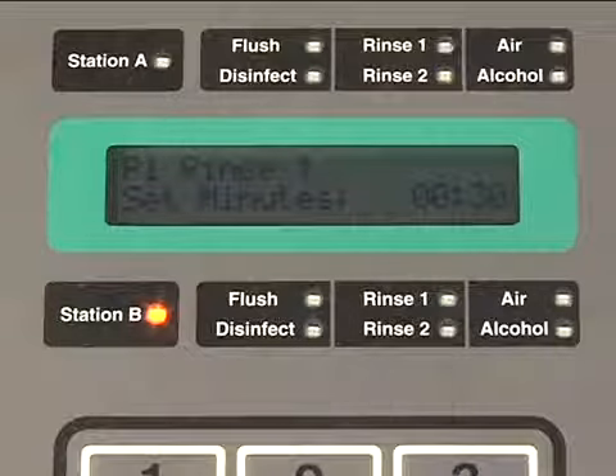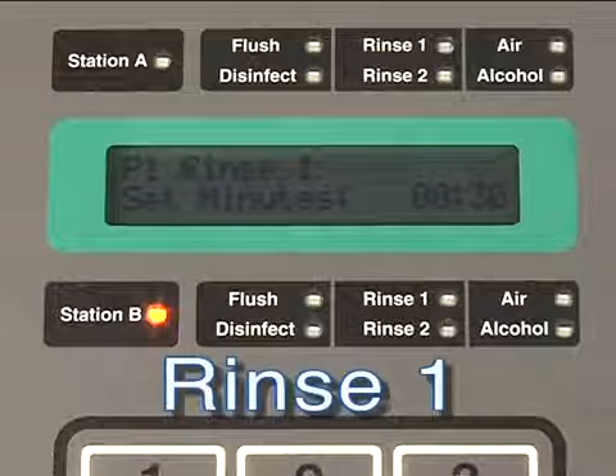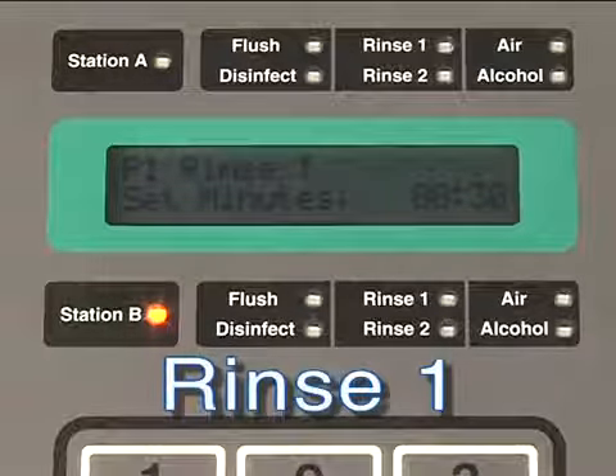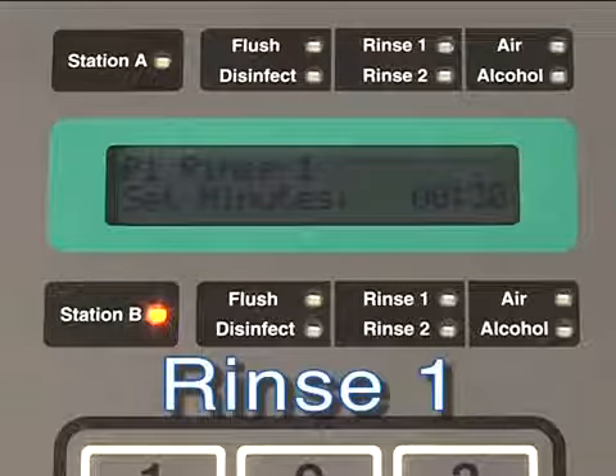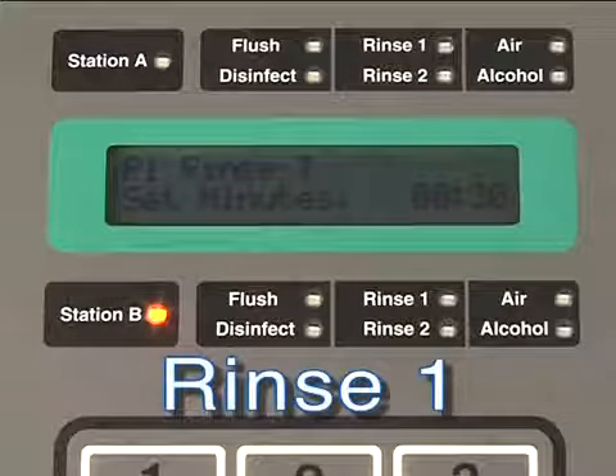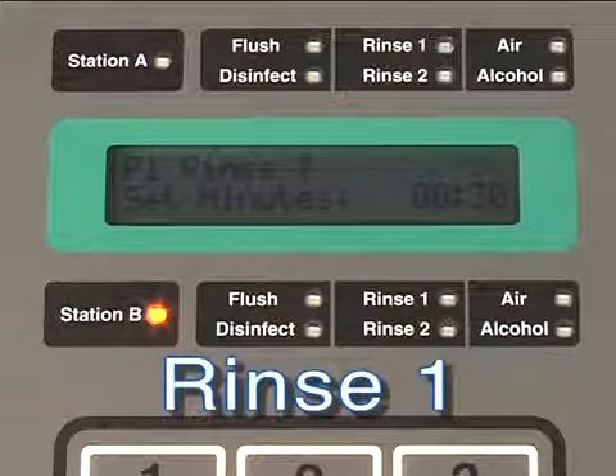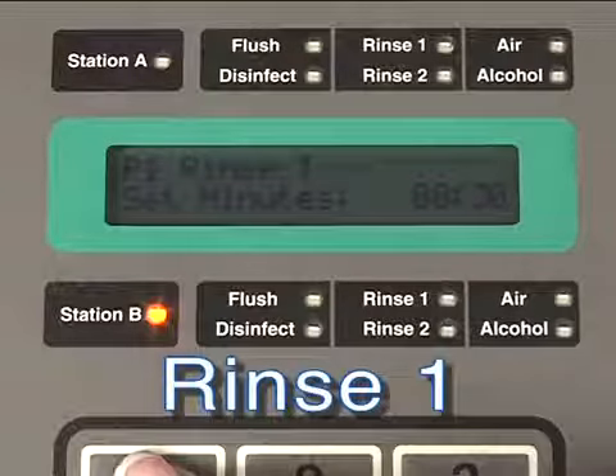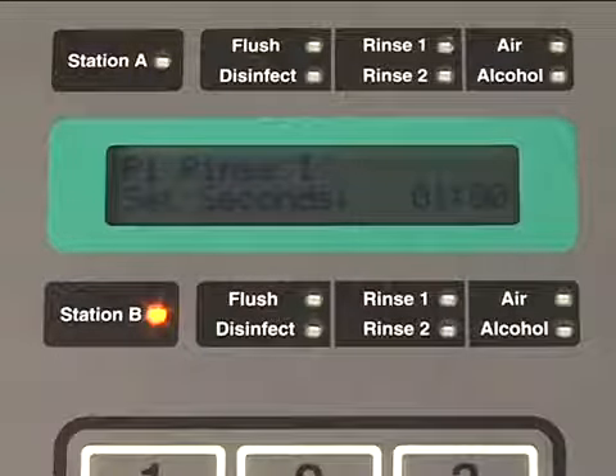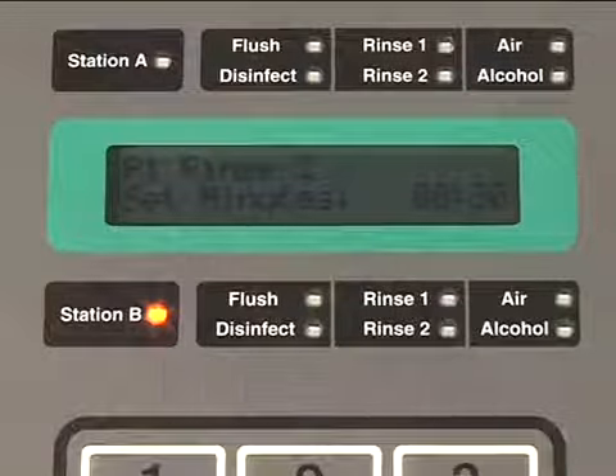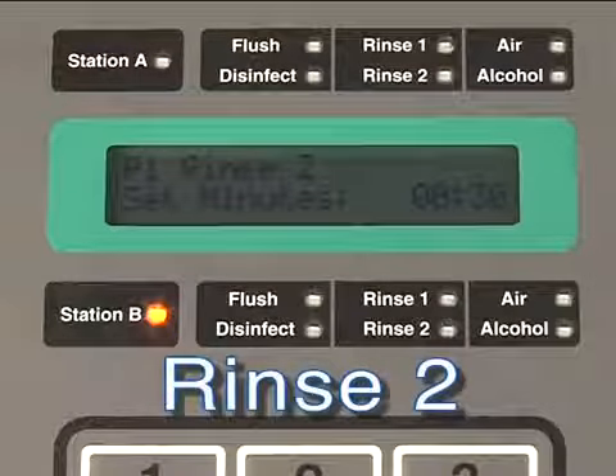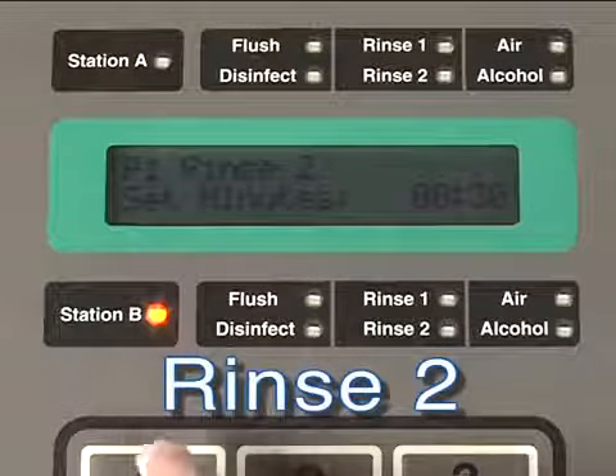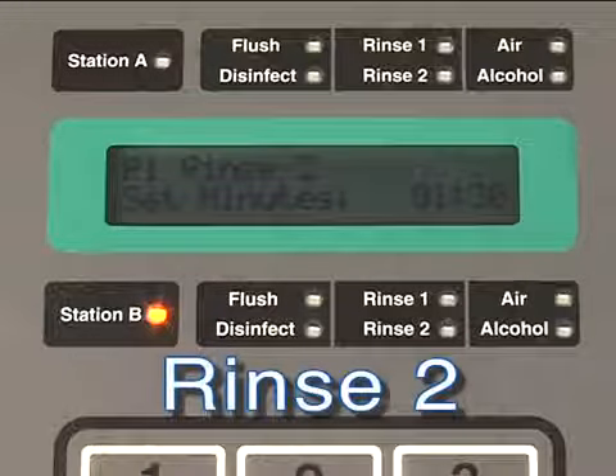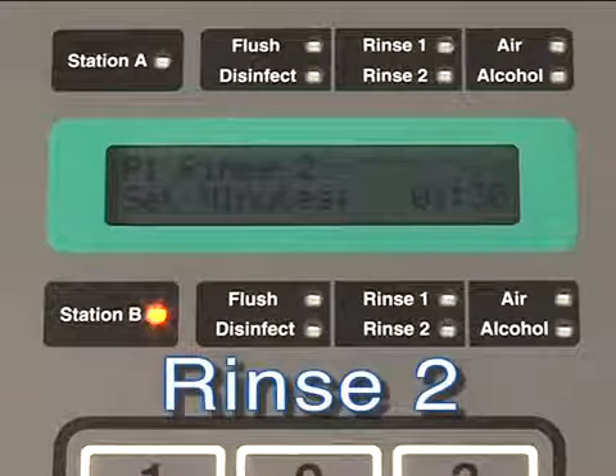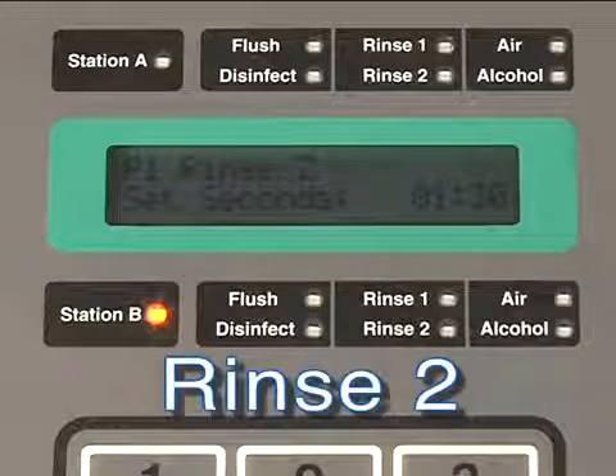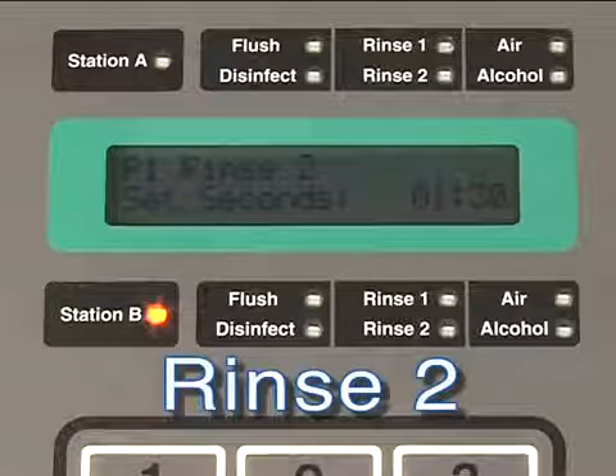Rinse 1 is the next parameter to set. Rapicide requires 2 rinses. We will set the first rinse time for 1 minute. For set rinse minutes, press 1, Enter. For seconds, press 0, Enter. For the second rinse, we will also set the program to a 1-minute rinse. Press number 1, Enter for rinse minutes, and 0, Enter for rinse 2 seconds.